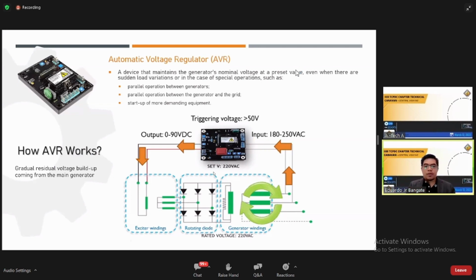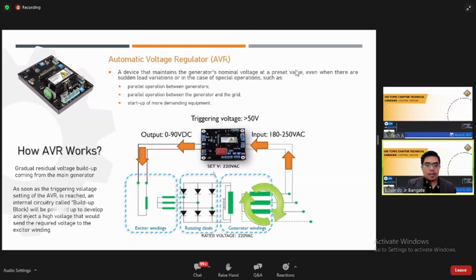some other voltage regulators might have a different triggering voltage. You have to check that from the manufacturer. Until it reaches the 50 volts triggering voltage, it will not work. So let's say it reached 50 volts. Now, as soon as the triggering voltage setting of the AVR is reached, an internal circuitry called the build-up block will be powered up to develop and inject a high voltage that would send the required voltage to the exciter winding. That is the 0 to 90 volts DC that is needed by the exciter to generate the necessary EMF into the rotor of the exciter winding, into the rotor of the generator.